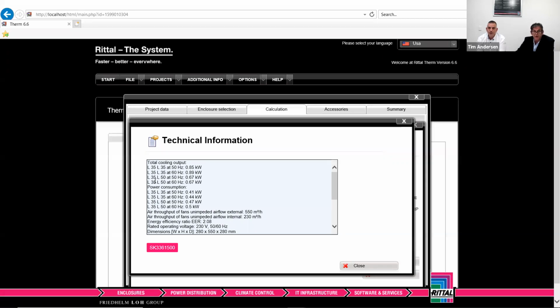Do you see that you've got L35 and L50 on the screen here at the top? Do you see how the equipment derates itself? Look, Rittal's really honest about the fact that when you cool at 35 degrees, you can provide a kilowatt of cooling very easily. But that's not really the case. Most of the equipment we have to design for is looking more at 50-degree ambient. And that's what the L50 there is for.